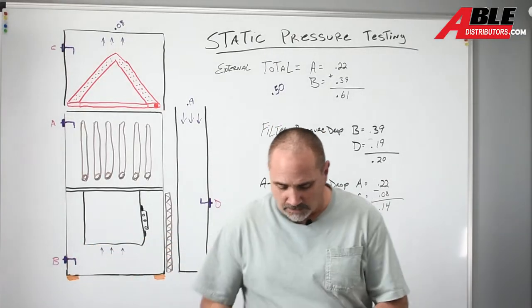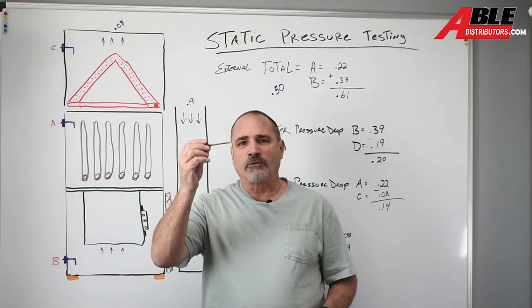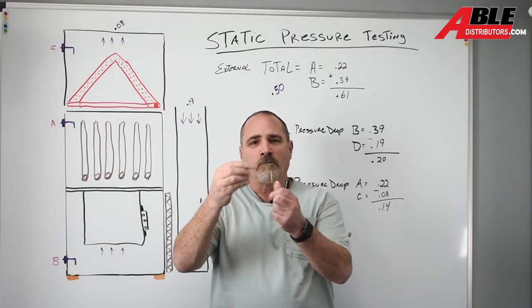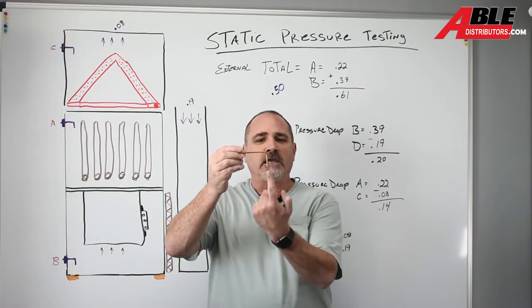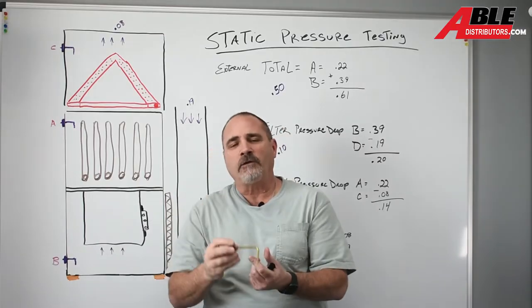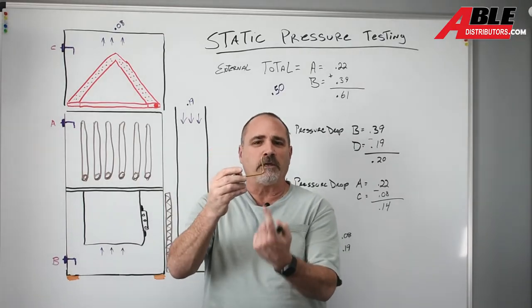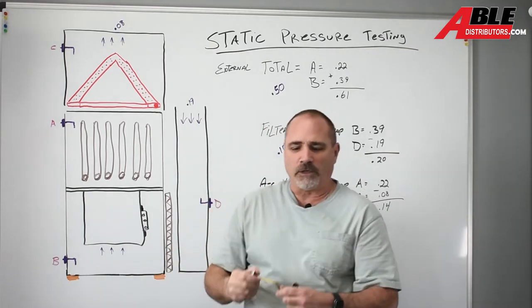Now when you do a static test you're going to have probes like this which have an arm. You want these facing into the wind. If you can't do it, as long as they're both facing the same way you can face it the other way, but typically we put them into the wind.